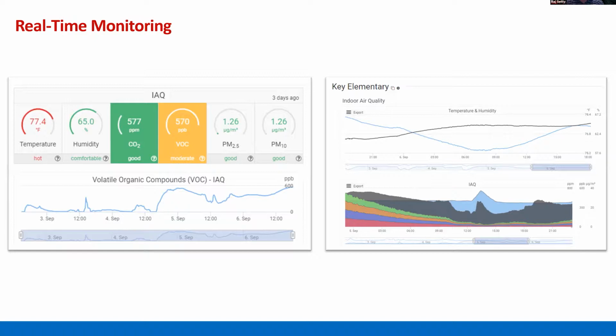No differential pressure. It's not about changing the filters. It's seeing if they're picking up the particulate. CO2. So when our carbon dioxide levels inside reach the same as outside, it is an indirect correlation that we have good dilution. And so now we're going to get the number of how long to run the ventilation during the after occupied. It may be 1 hour, it may be two, it may be three, to make sure we flush it. Distribution is going to be your challenge.